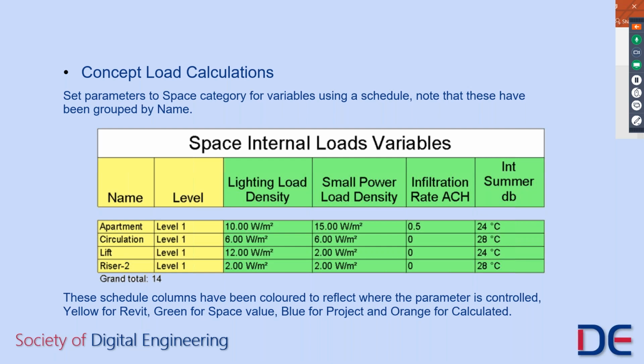You'll notice that the columns here are coloured, and I'm going to try and keep those colours consistent throughout this presentation. The colour shown here, if it's yellow, the value is coming directly from Revit. If it's green, that means I'm applying a parameter to a space object. If you see a blue column, that means it is a project parameter. And if you see an orange column, that means that parameter has been calculated within this schedule.